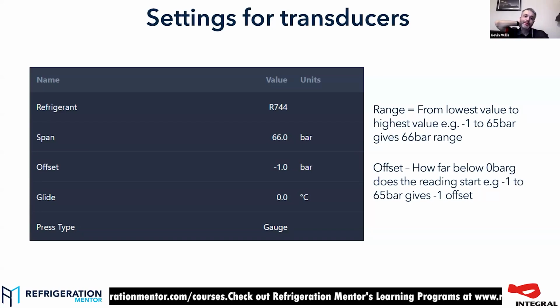And just bear in mind as well, not so much with the RDM ones, you could get away with the 125 bar transducer on a 60 bar system, but I've seen a few times people put the 65 bar transducer on an LT HFC system, and you're operating at like 15 psi, 1 bar.